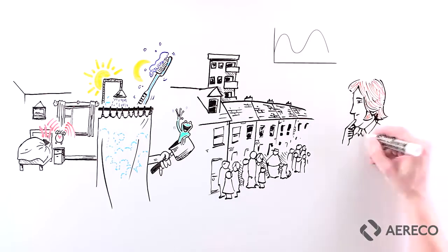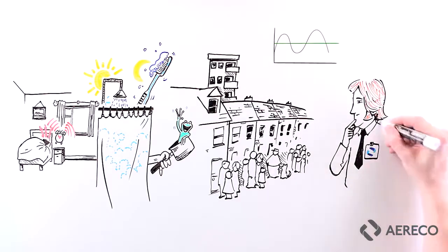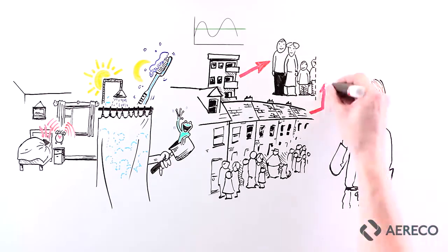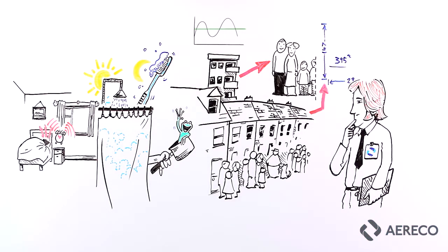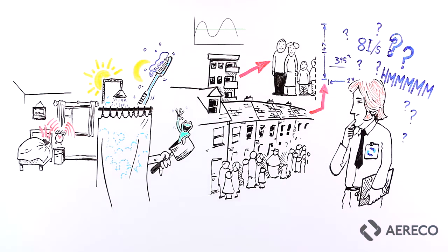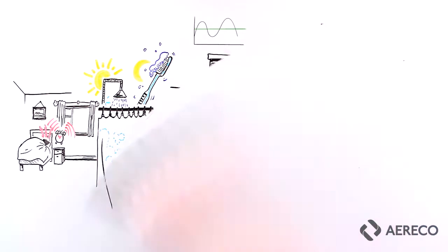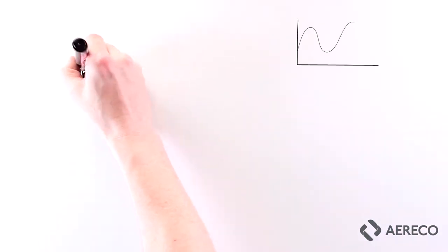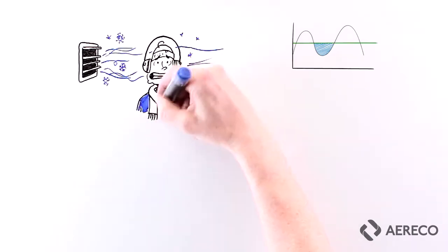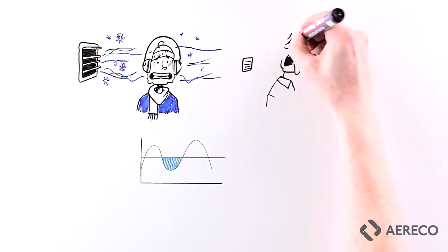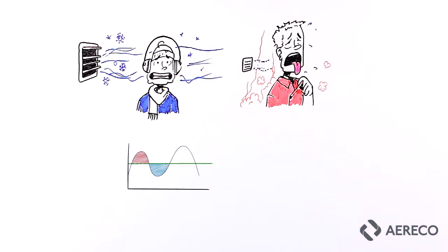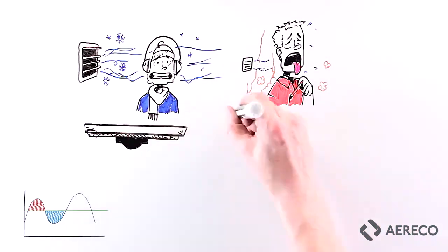In the past, we had to pitch a guess at how much ventilation was needed. This might be on an average family, it might be on the performance of the house or its size. It's where we hear things like half an air change an hour or 8 litres a second. The trouble is, a guess is a guess. Ventilate too much and you might cause thermal discomfort, noise problems and waste energy. Ventilate too little and you might affect air quality, and as we pointed out in the first video, leaving the occupant to control it is not without its risks.